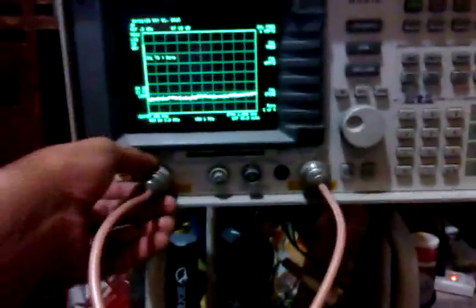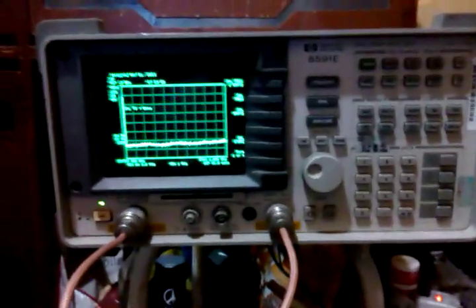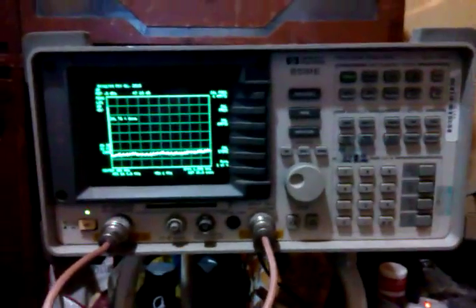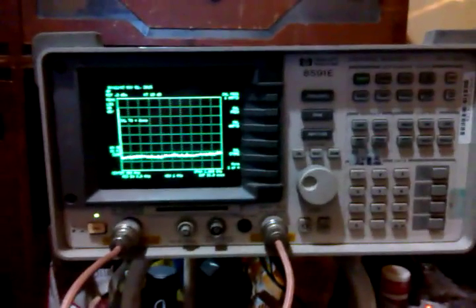This is the Hewlett Packard 8591E. With the supplied patch cord or cable, I have already placed it from the RF out 50 ohms towards the input 50 ohms. This way we can self-calibrate the spectrum analyzer using its own built-in tracking generator. Actually, the tracking generator is another module which was already installed on this Hewlett Packard 8591E.